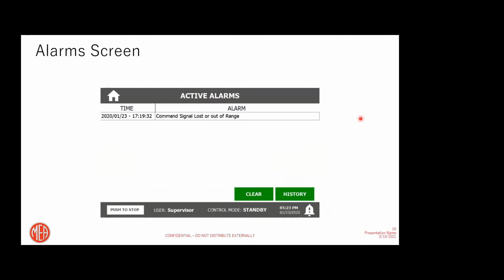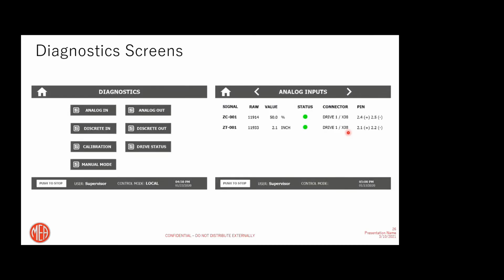These are active alarm screens. If you noticed on the menu there was an alarm screen, you push this button and it shows the actual alarm and tells you exactly what's happening with the unit. For example, this one indicates that we lost the input signal. You get the timestamp and actual time. Additionally, you can have a history button, which gives you the full list of alarms you have had throughout the whole operation of the unit, which you cannot erase at all. So you get basically the same functionality as your current PLC-based systems.